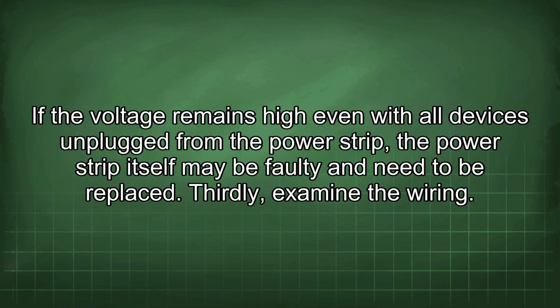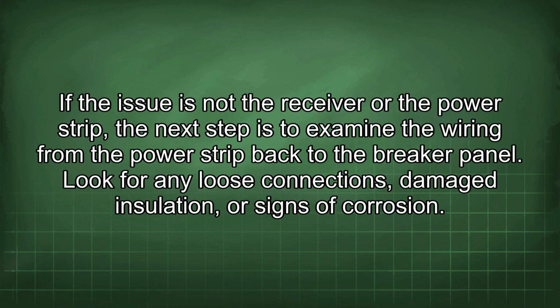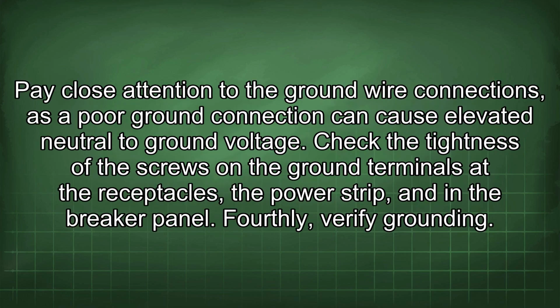When the voltage jumps back up to 2.5 volts alternating current, the last device you plugged in is the culprit. If the voltage remains high even with all devices unplugged, the power strip itself may be faulty and need to be replaced. Thirdly, examine the wiring. If the issue is not the receiver or the power strip, the next step is to examine the wiring from the power strip back to the breaker panel. Look for any loose connections, damaged insulation, or signs of corrosion. Pay close attention to the ground wire connections, as a poor ground connection can cause elevated neutral to ground voltage.